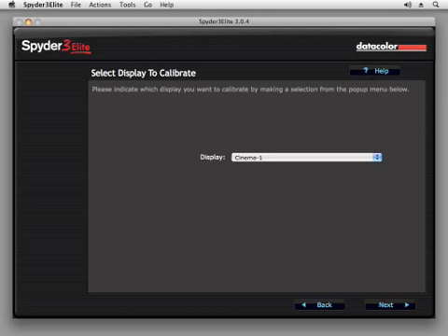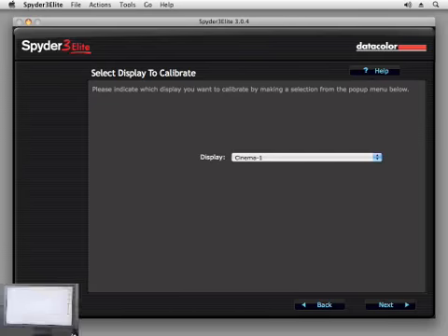When two or more monitors are viewed simultaneously, the eye will perceive differences between them that are not evident if the monitors are viewed individually. The primary characteristic that contributes to perceived differences between simultaneously viewed monitors is the white luminance level. This characteristic is often called brightness.